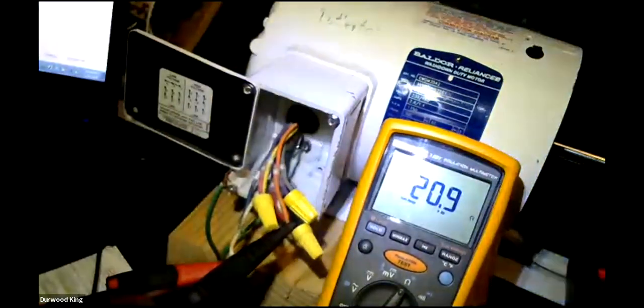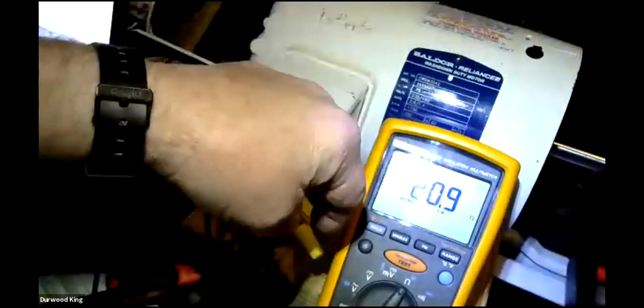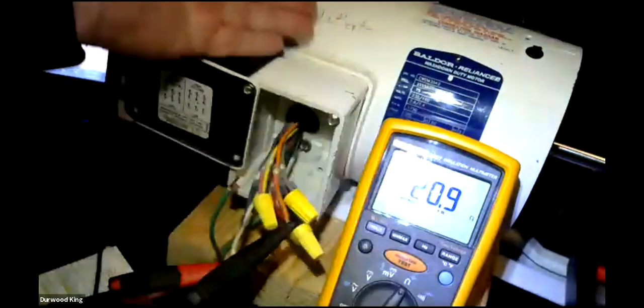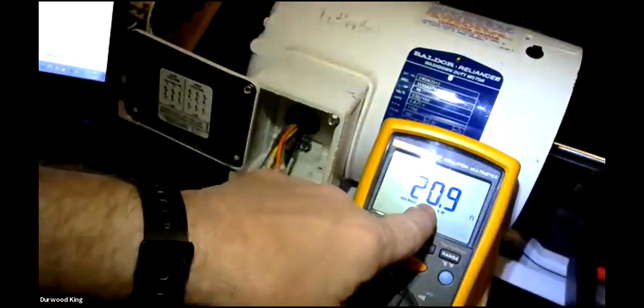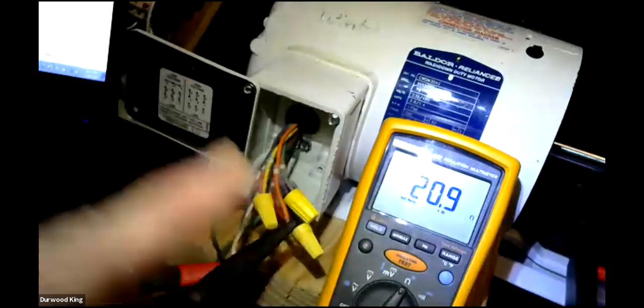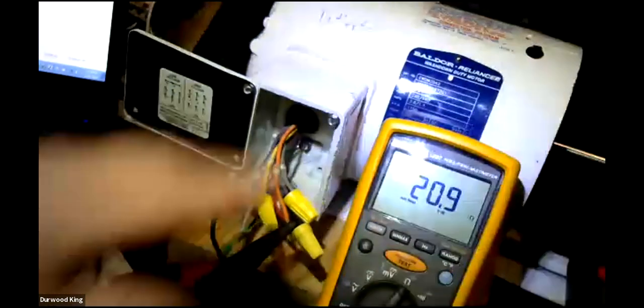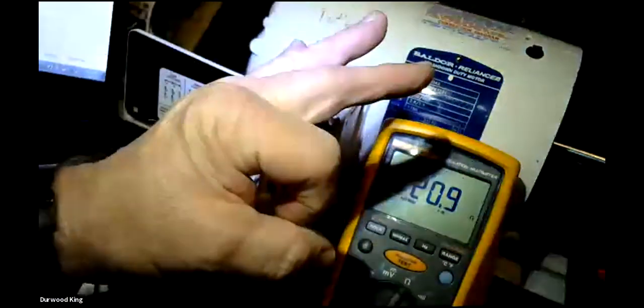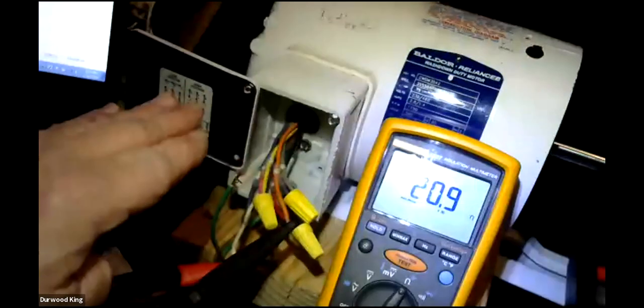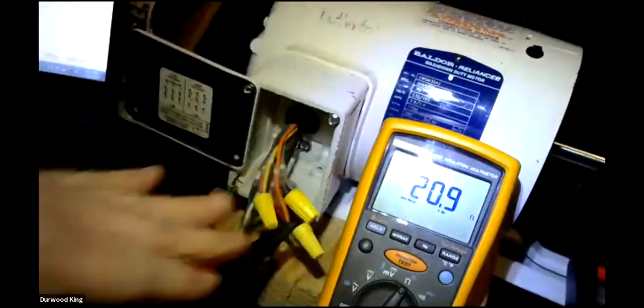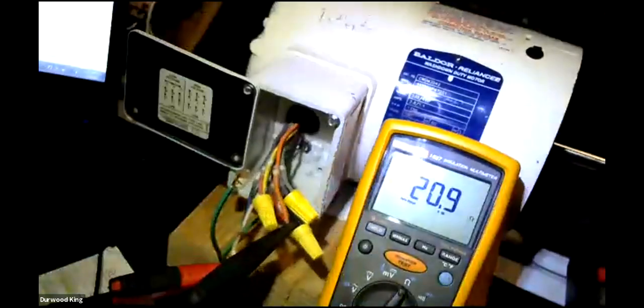That's okay for that. Now, if it was a 5 horse, you could look for it to be way less than that. If it was a 10 horse, even less. I've seen some large motors where the resistance was way down around 1 ohm, or maybe slightly less than 1, because the windings were so large that there's very little resistance in there. They conduct so well that the ohms is very low. So those are your tests there that can tell you.